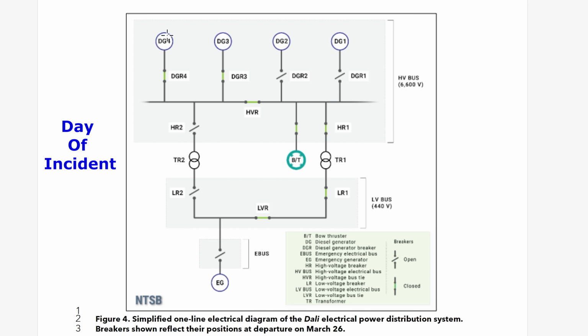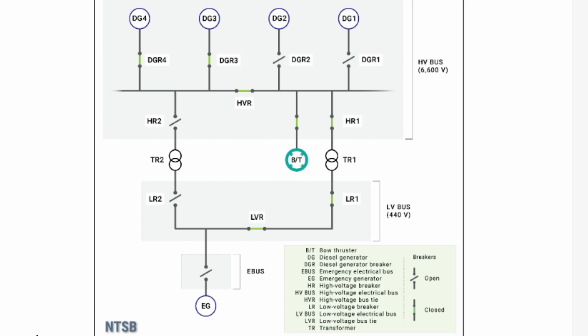Okay, so then all of a sudden, these 2 generators right here, 3 and 4, continued running, and so they were actually still supplying power here to the high voltage bus, even though the low voltage bus down here was already down. But the fuel in these 2 eventually ran out because they weren't getting enough pressure now, and they were just basically running off of the residual fuel. Okay, so then the emergency generator kicked in, so now they had at least power on the low voltage bus. And then about a minute later, you would start to see diesel generators 3 and 4 starting to underperform because they had insufficient supply of fuel in them. So that was part of the problem. And so then on top of that, the power management system detected the underperformance and the frequency drop there.